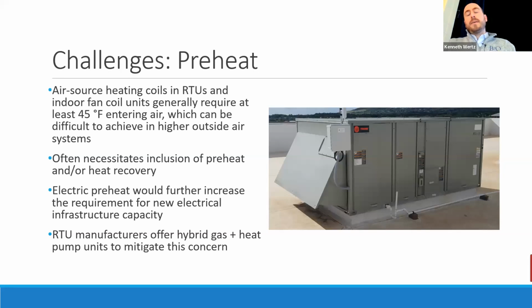So, preheat. In most cases, this is not an issue, but when you've got systems that deliver more fresh air, more ventilation, to provide that ventilation we talked about, keep people feeling healthy, you run into the challenge where the mix of 0 degree air outside with the 70 degree air that's coming back could bring you below this 45 degree rule of thumb, which is sort of the minimum that these systems want as the air coming into the heating system, into the coil.